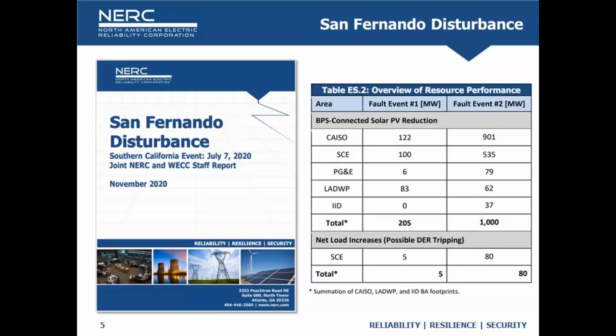So a number of different tripping mechanisms, and momentary cessation continues. I'll talk about this in a second. We continue to see plant level controller interactions, which is boiling up to be one of the biggest challenges I think we have. In this event, we had about 1,000 megawatt reduction of bulk system connected inverters. We actually had two faults a couple minutes apart from each other. The second fault was a re-energization of a line that had a static wire fallen across all three phases.